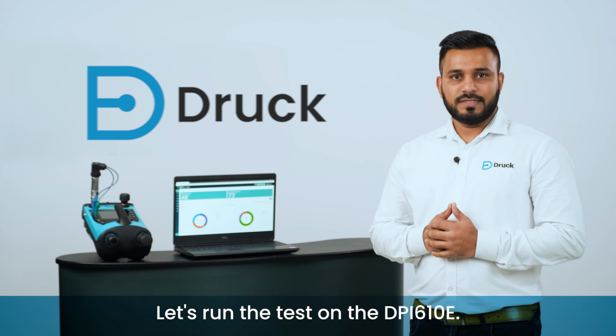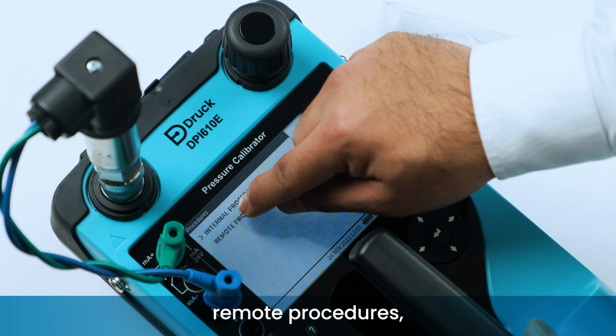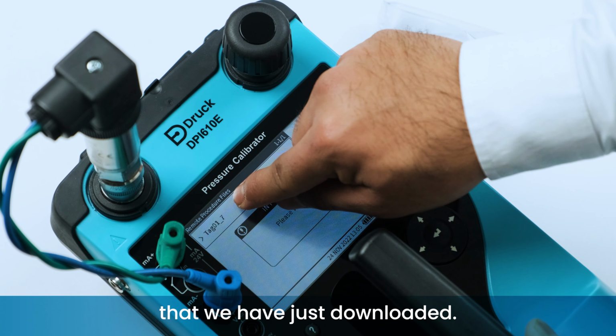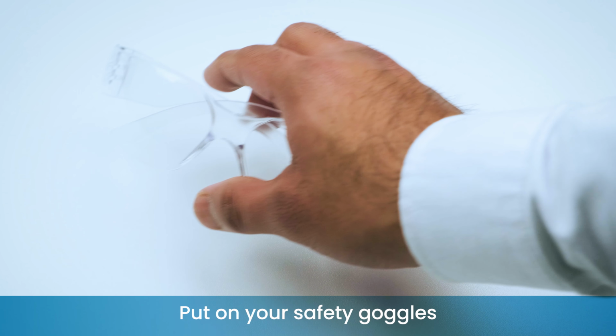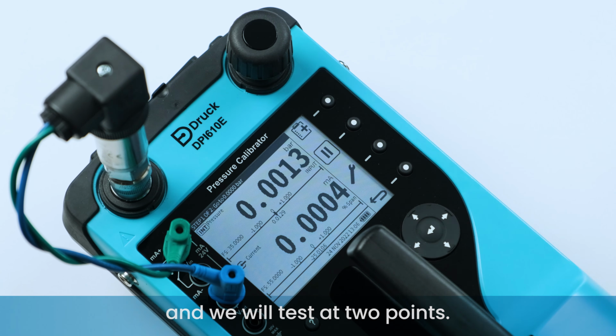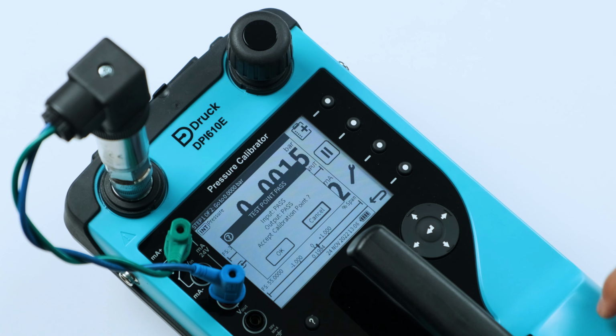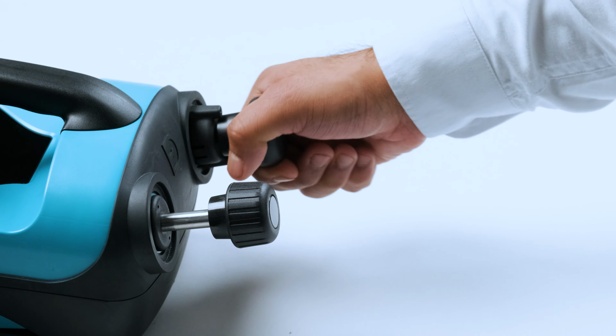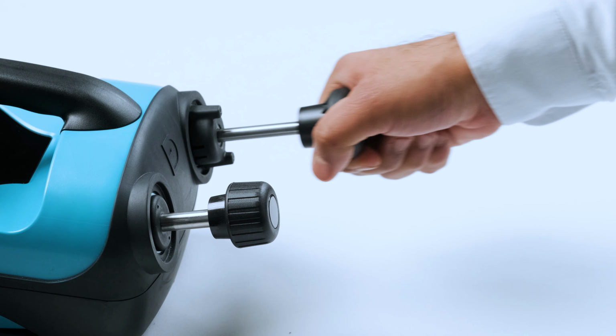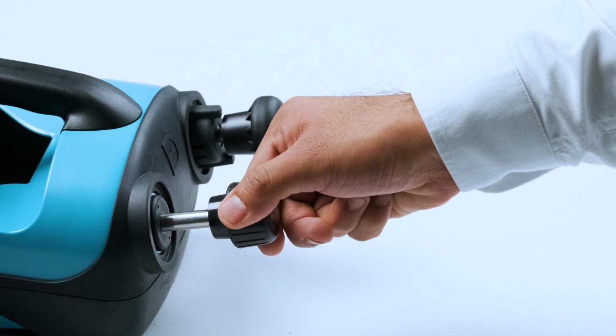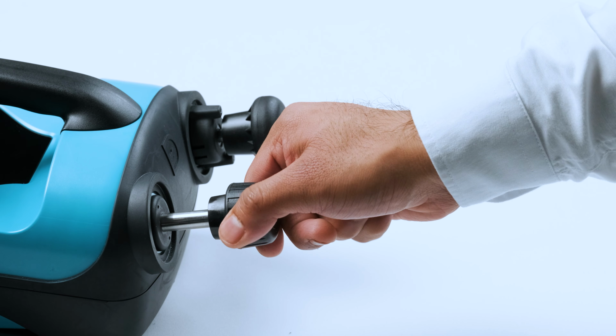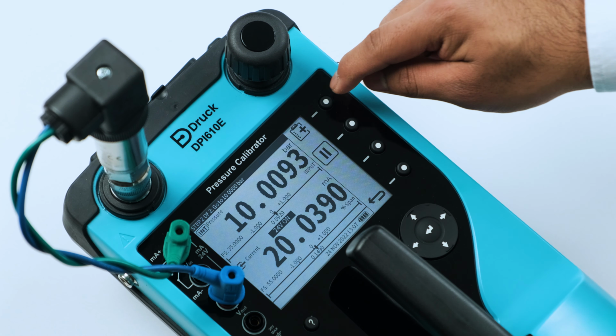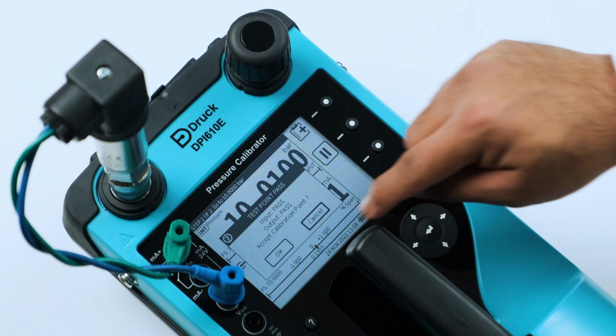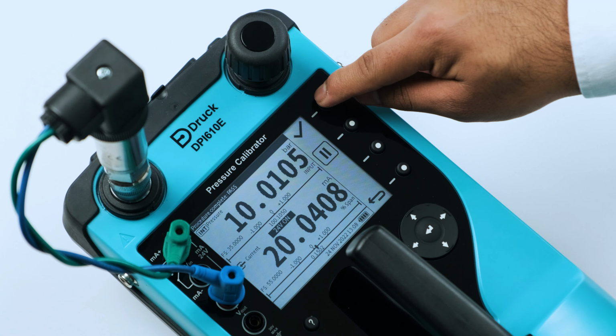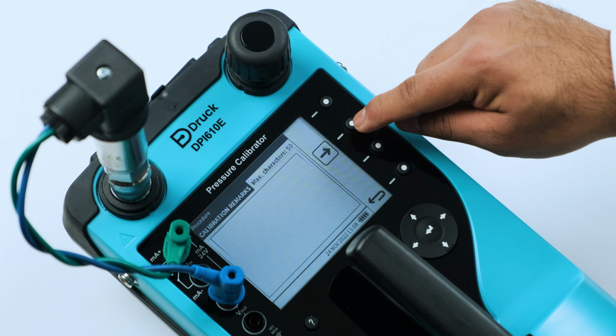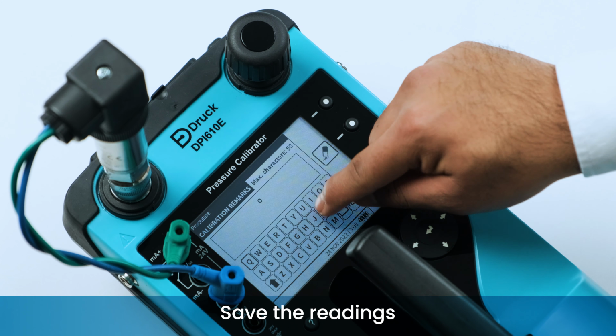Let's run the test on the DPI610E. Click Documenting, Remote Procedures, and you should see the task that we have just downloaded. Put on your safety goggles and we will test at 2 points. Save the readings and exit from the procedure.